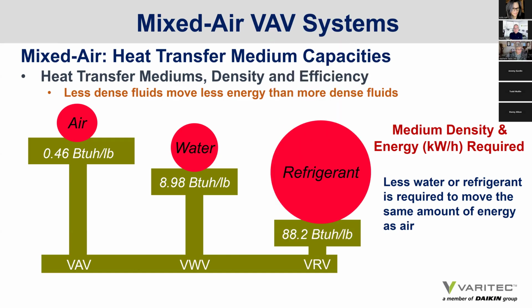But again, another factor: what about refrigerant as a heat transfer medium? I've spoken to this in the past. What if we actually bring refrigerant into a building, into each zone, and allow it to be the heat transfer medium? We find that by using water or refrigerant local to each zone, we can create more efficient systems, through the reduced pumping horsepower compared to the fan horsepower otherwise required, and also through the vapor compression cycle in variable refrigerant flow systems.